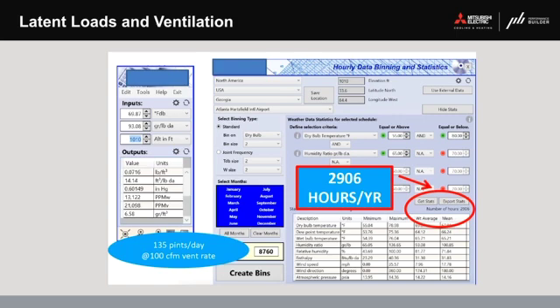So you see this 8760 at the bottom left of the screen. That's the number of hours out of the year. And for Atlanta, Georgia, we have 2,900 hours out of the year that fall into that described weather bin. So that fall into that temperature range between 55 and 80 and that humidity amount above 65 grains per pound. So that's a huge number out of the year. In fact, it's just around 33%. So we're talking 1 out of every 3 hours in Atlanta, Georgia. If we're ventilating continuously, that's a load that we've got to consider.